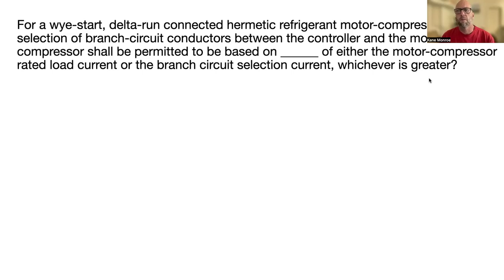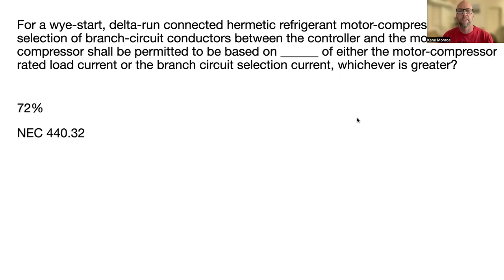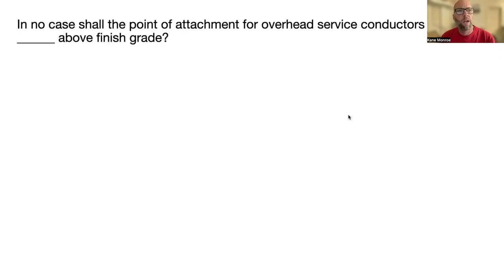For a wye or delta connected refrigerant motor compressor, the selection of branch circuit conductors between the controller and the motor compressor shall be permitted to be based on 72 percent of either the motor compressor rated load current or the branch circuit selection current, whichever is greater. That's NEC 440.32, right in the next article after 430, which covers motors.